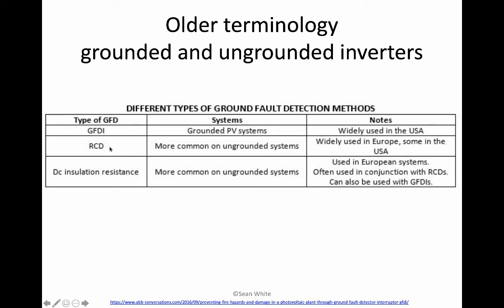And then the other thing that's really good for finding ground faults, super sensitive, is the insulation test. So what an inverter does is when it wakes up in the morning, it will send out a quick pulse of voltage through the array and see how much leakage to ground there is through the insulation of the wire. There should be millions of ohms, that's megaohms. Some people call it a megger test when they do a test like that. And the inverter will do an insulation resistance test every morning, and they can find milliamps of leakage current with this resistance test. It's so good at finding ground faults.